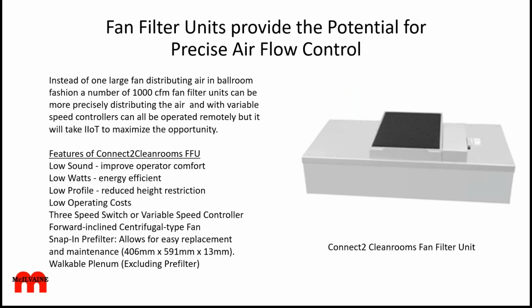One of the variables is the amount of airflow, which affects energy use. Instead of one large fan distributing air in a ballroom clean room, you have a number of 1,000 CFM fan filter units. Here's the Connect 2 example.